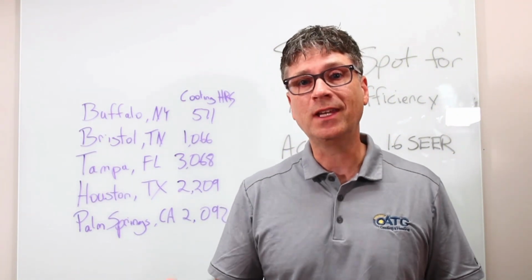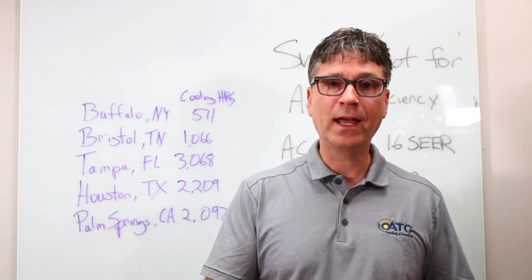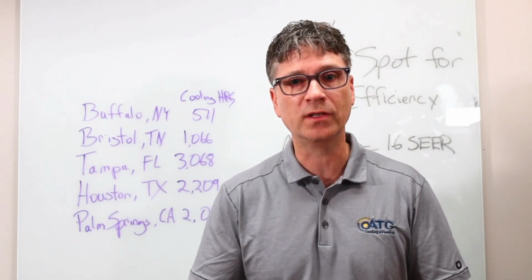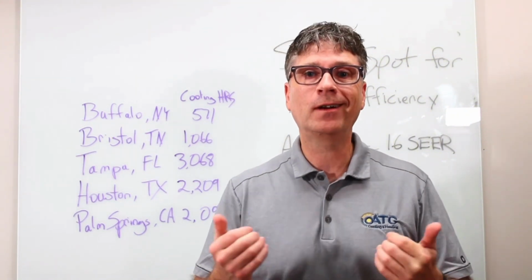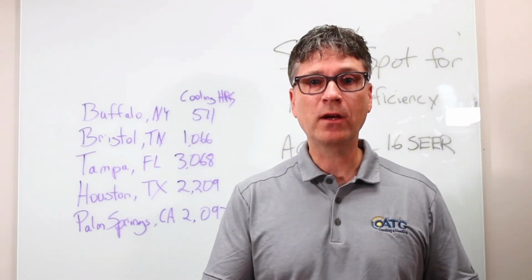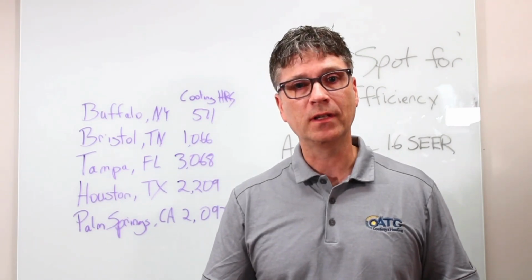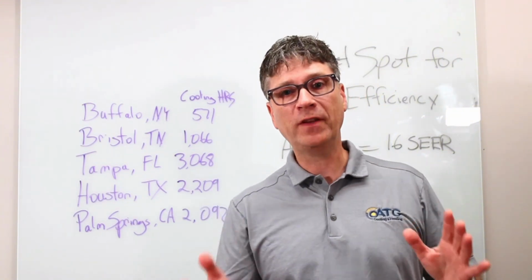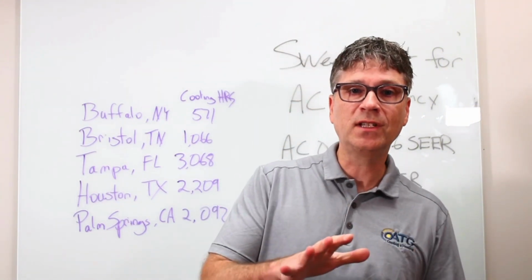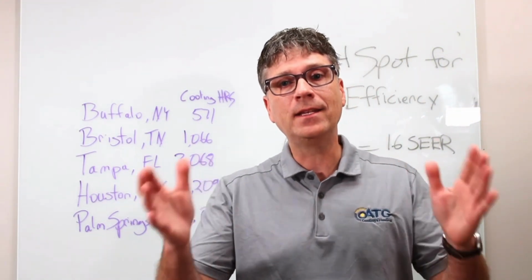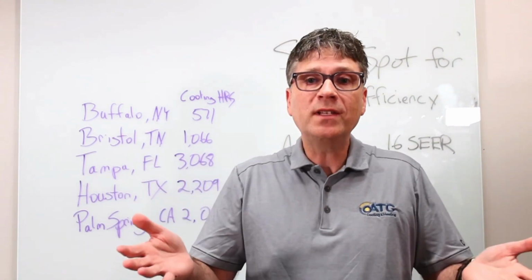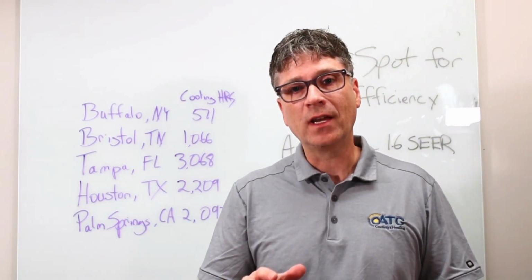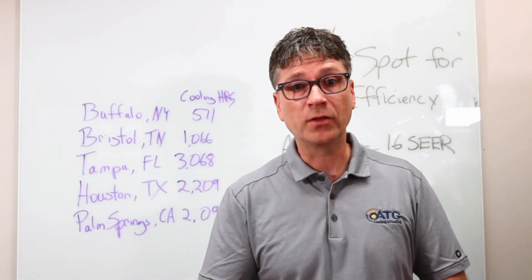If your system is a heat pump and you have both cooling and heating efficiency to think about, you have an even bigger reason to choose higher efficiency equipment. And of course, there are tax credits and other incentives that may encourage you to select higher efficiencies. When considering the overall installation cost, I find a sweet spot at about 15 SEER for heat pumps and 16 SEER for AC, and again at 18 SEER for both kinds of units. 20 SEER and above is really nice, but returns only a modest savings in all but the very hottest of climates. So there you have it.